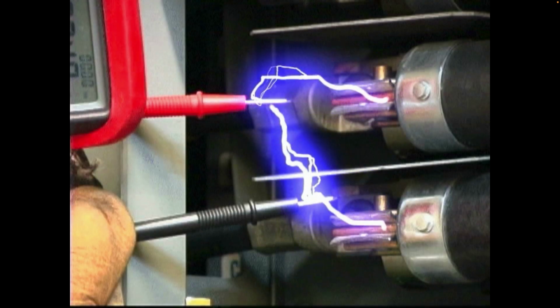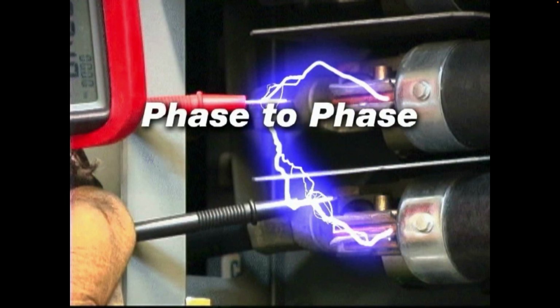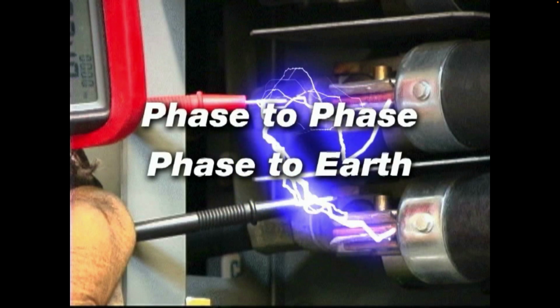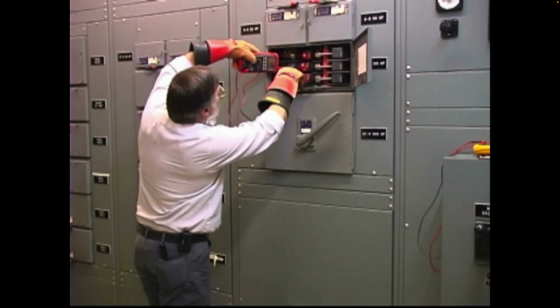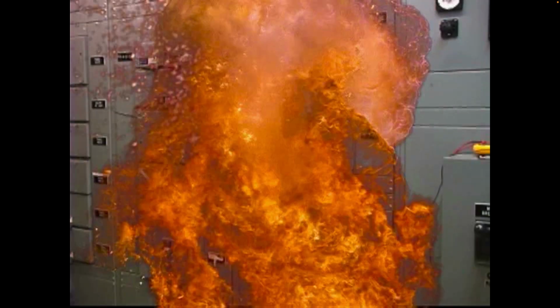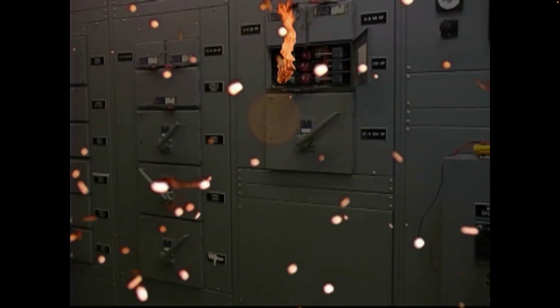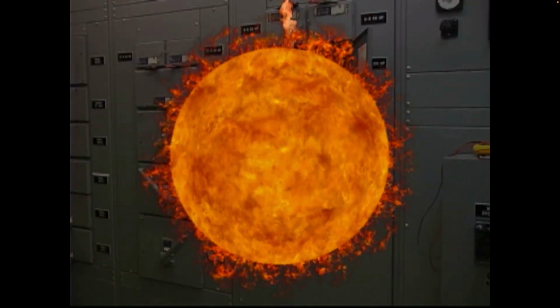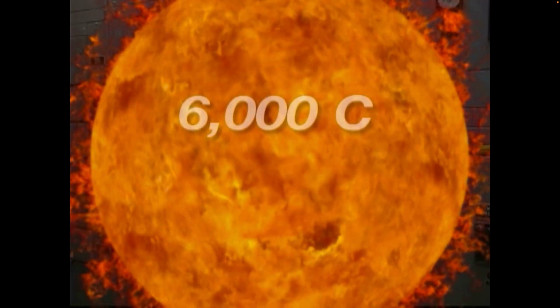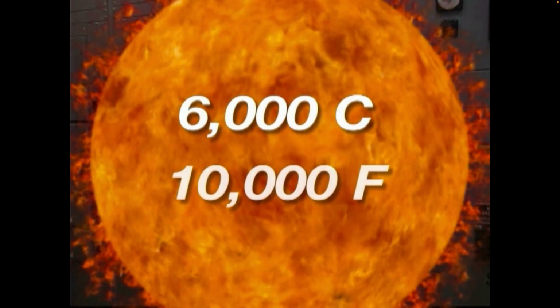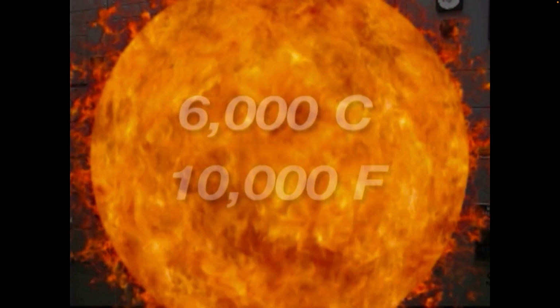When two arcs join, they cause either a phase-to-phase or phase-to-earth fault. The result is an arc blast, which can lead to a plasma fireball fueled by the energy in the electrical system. When this occurs, temperatures can reach about 6,000 degrees Celsius or 10,000 degrees Fahrenheit.